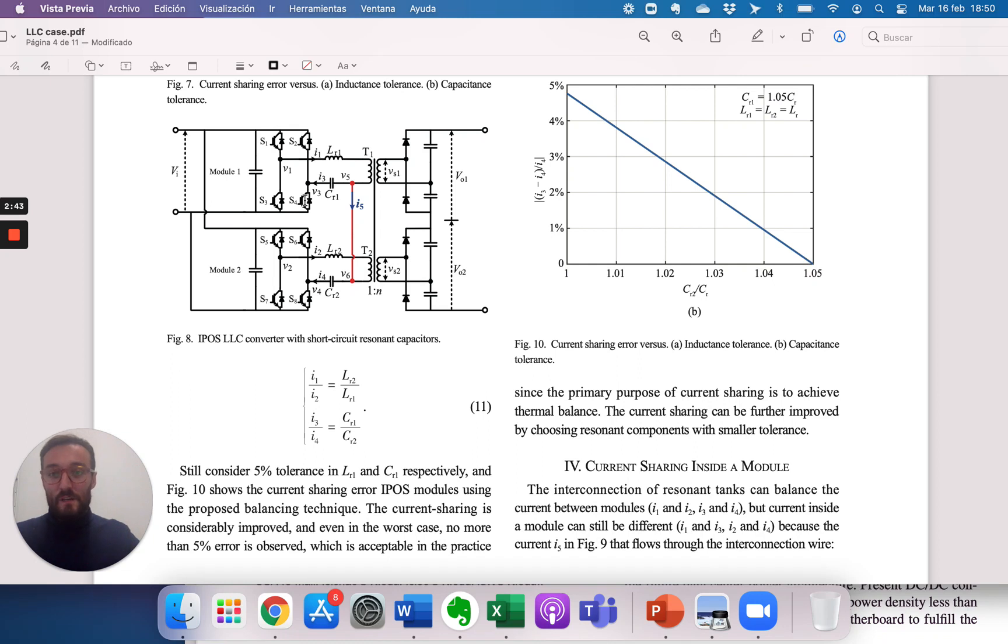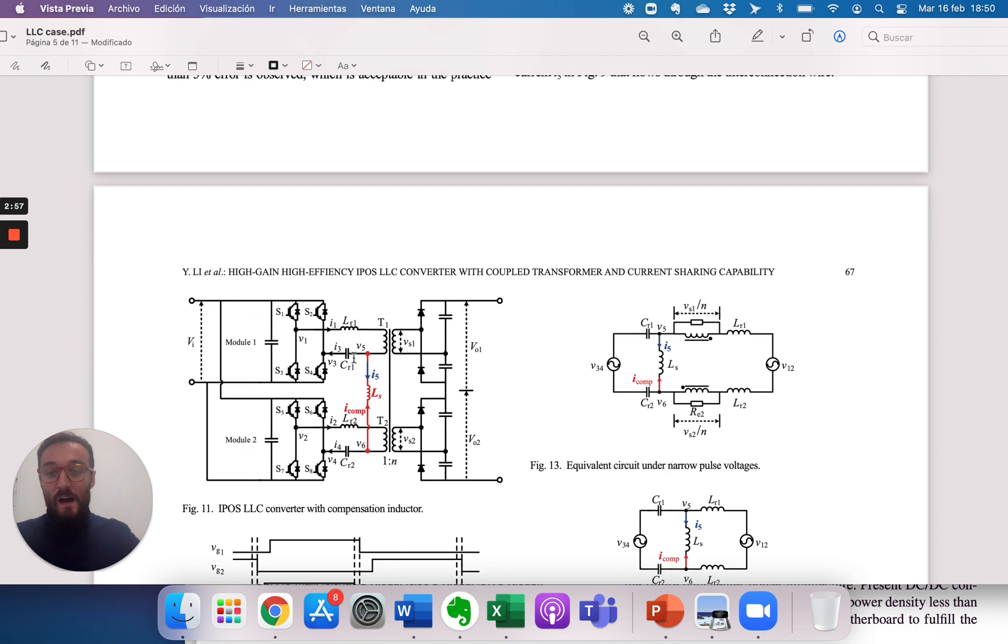In order to keep the current sharing equally between the two parallel inputs they connect both windings with a wire. Then they realize that there is a lot of circulating currents and then they add an inductor in order to increase the impedance in the connection.